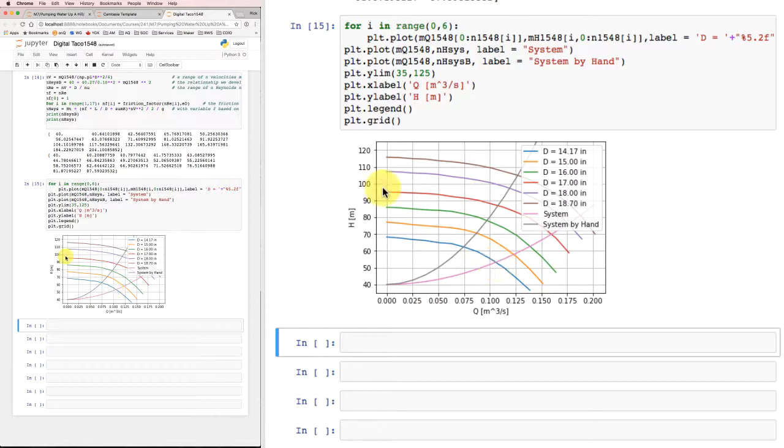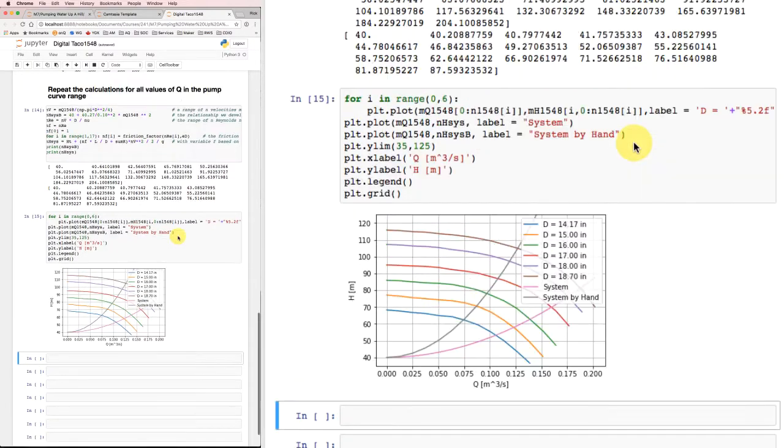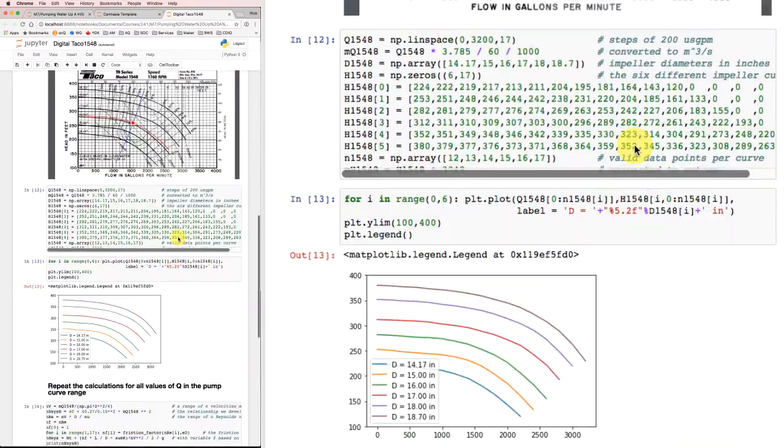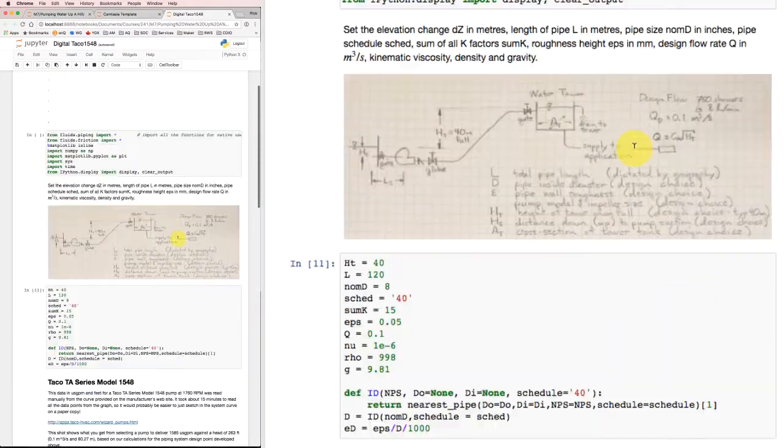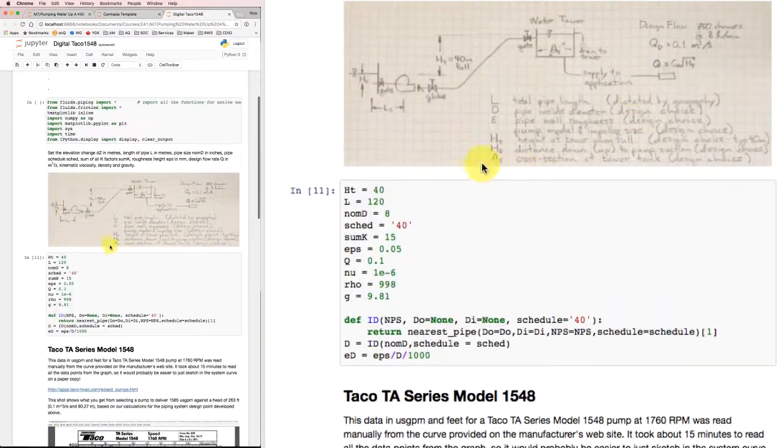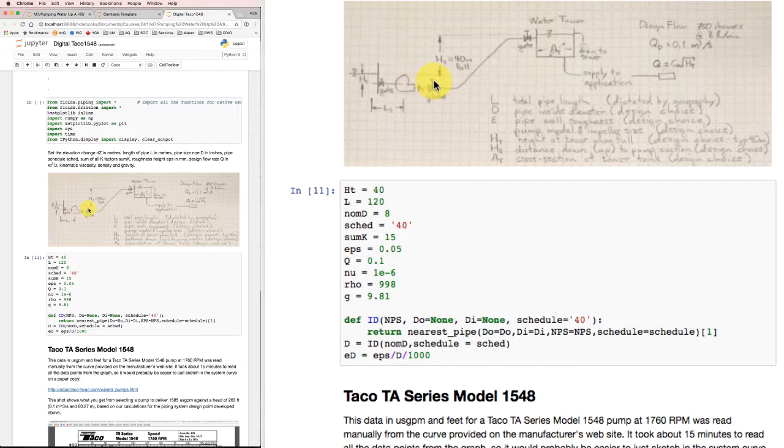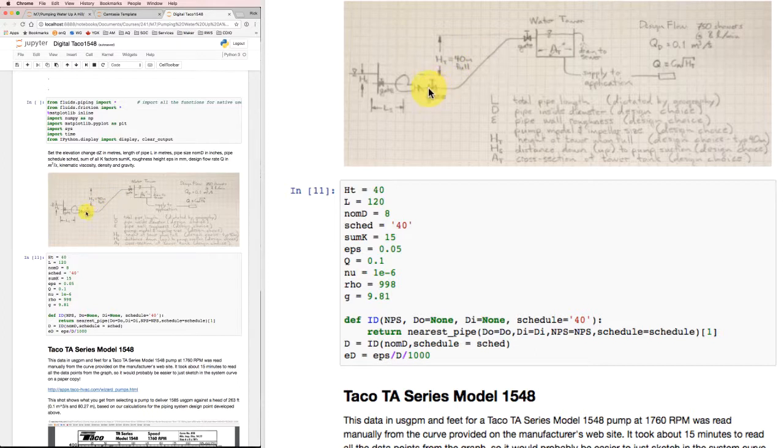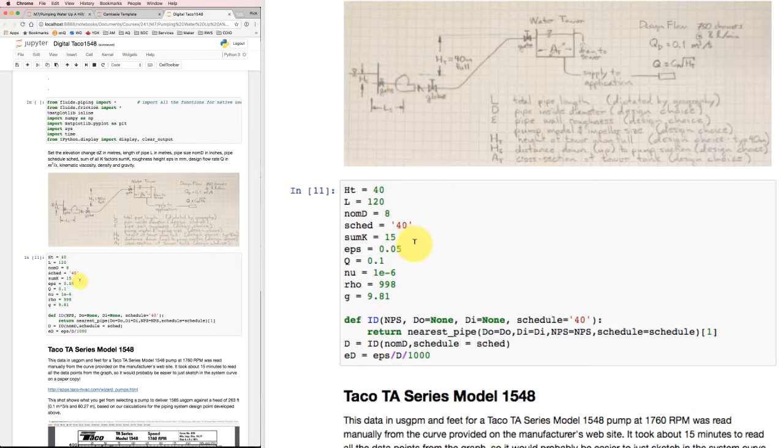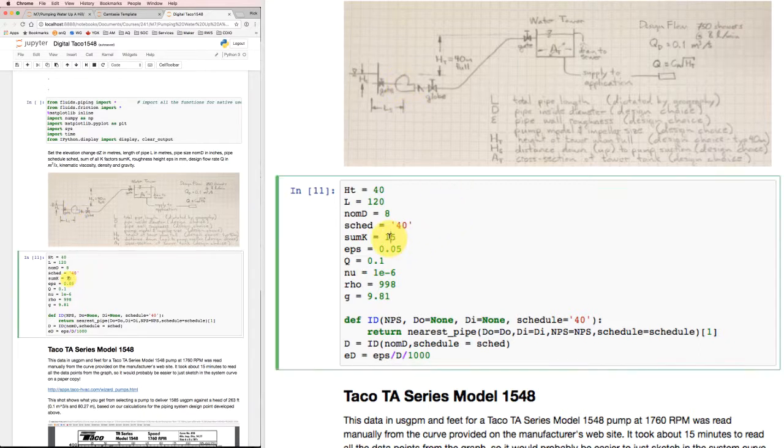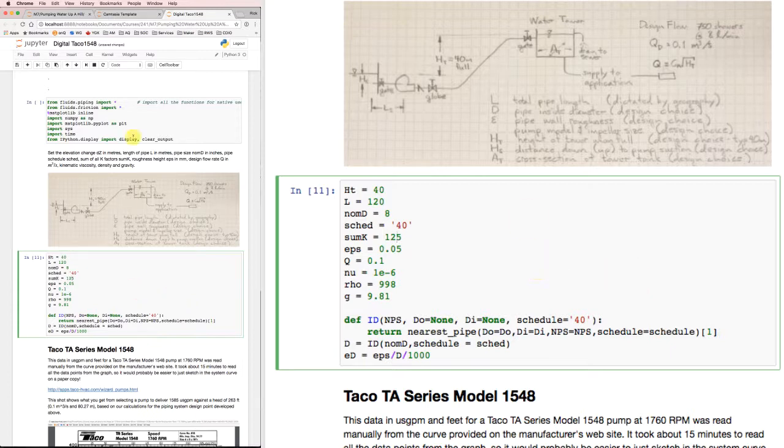On the other hand, if I'd already bought the pump and I'd installed the 8-inch pipe and I'd discovered that I was getting way more flow than I wanted out of my system, things were running too quickly, I could go back up and I could adjust this globe valve. I've got a globe valve here which I can use to dramatically increase the losses in the system. What I can do is I can put some friction in here, some minor losses, and that will soak up some of the energy that's being added by the pump.